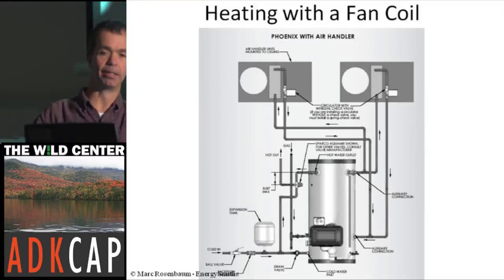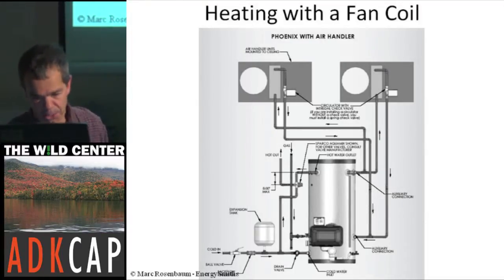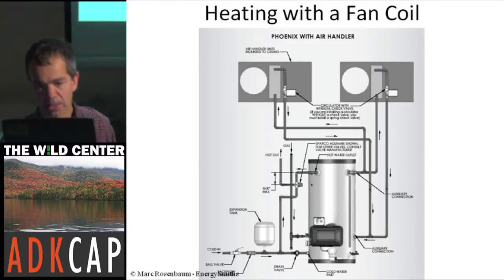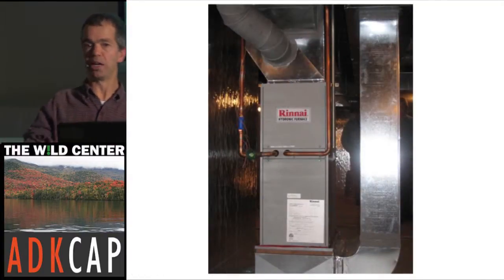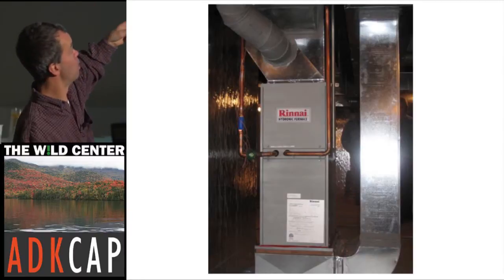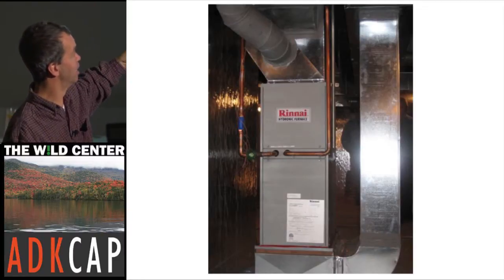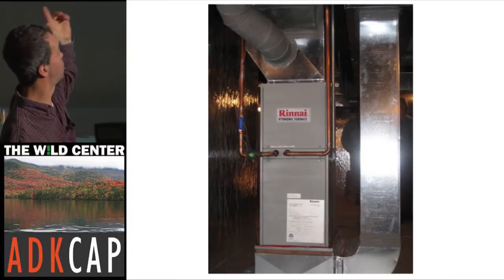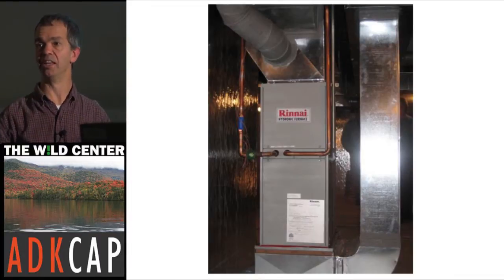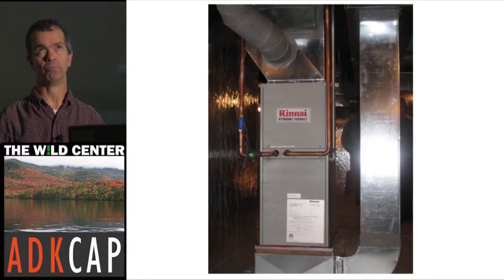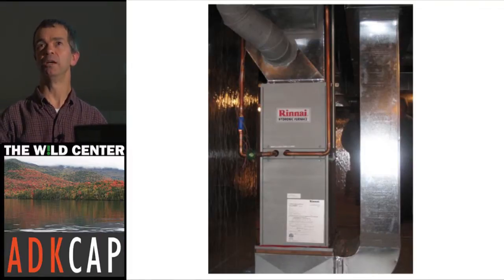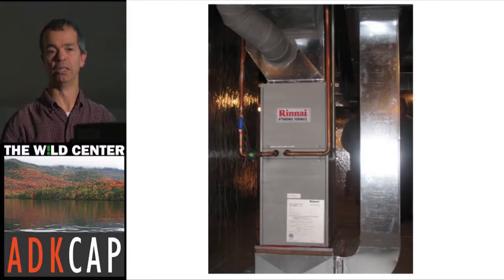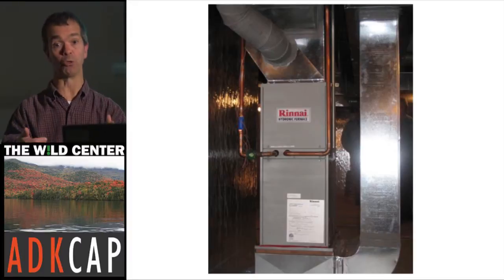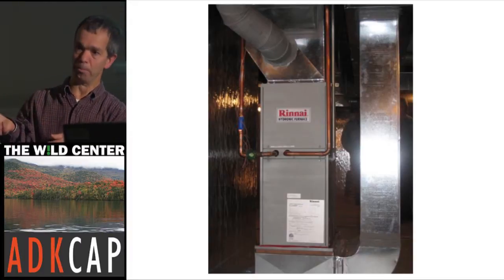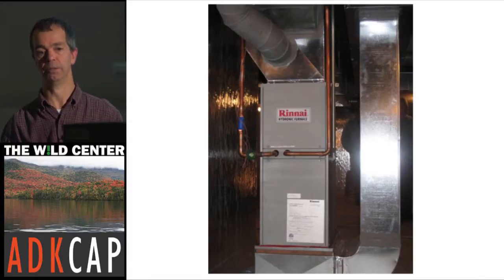This is the schematic of using fan coils, and this is again with the application of the big tank, which we didn't use. I've got schematics. There's the fan coil unit. So it aligned right with the furnace ductwork. We brought that new piece down as the intake, or the return, I guess you'd call it the return. But all the supplies, we married into the ductwork that they had. We did seal it to less than 3 CFM per 25 Pascal, measured at 25 Pascal. So basically, we took care of leakage, because we certainly don't want leakage in the ductwork, because that will be amplified if we're trying to distribute air.